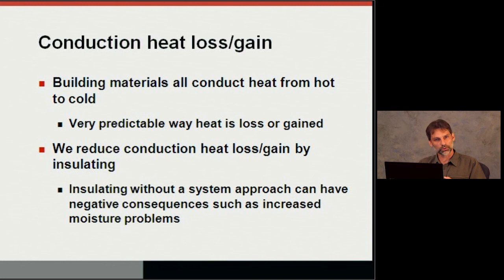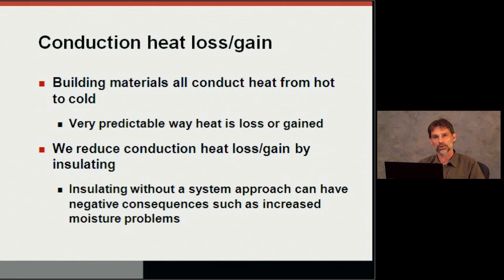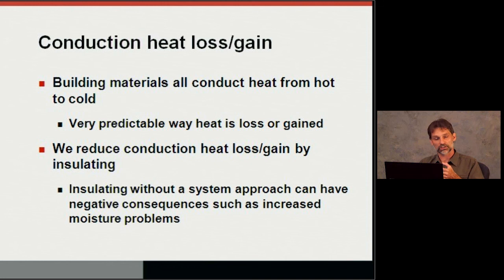Once the foundation wall temperature drops and we allow air movement — which carries moisture — that moisture comes in contact with the cold foundation wall and we can have condensation, water dripping, and mold growth. Without a broader systems view, we can create issues. The bottom line: if we insulate, we can increase wetting potential and decrease drying potential without having an effective air barrier in front of that insulation. It's very key when insulating to have a good air barrier in front of the insulation, sealed on all sides.